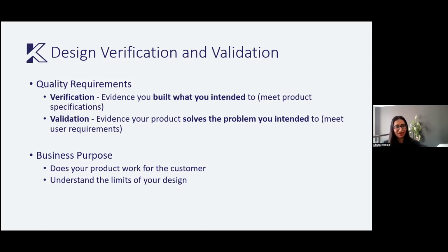Okay, so ideally your requirements are set, your development is done, and now you're into your testing phase. I have never seen V&V ever go smoothly. Nobody does it once and is just done. There's always surprises. So from a quality system, what we're looking for is to make sure that you have documented procedures that you're actually going to execute, and then you execute them and you're discussing the results.